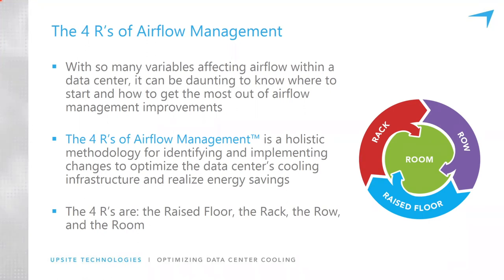And this helps focus efforts. It's a good idea to go out into the raised floor, do some surveys, and really focus efforts on improving airflow management at, say, just the rack level. And then if you happen to have a raised floor, to do the same at the raised floor level. And then what we'll be talking about today is the row level. And each of these outer elements, these three R's in the outer circle, are ways to improve airflow management. The room level, which they all reference and point to, is a reminder that we need to make adjustments at the controls of the room level to realize the benefits.